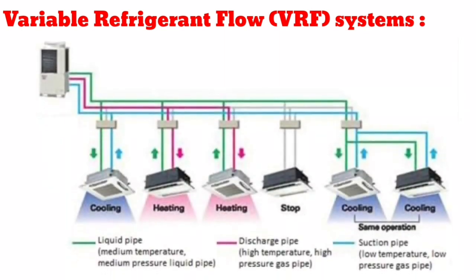Variable refrigerant flow VRF systems are similar in appearance to multi-split air conditioners. What makes the difference is the number of indoor units and the control function. A multi-split system is generally limited to about 10 indoor units, whereas VRF systems can connect to more than 50 indoor units on a single outdoor condensing unit. VRF systems use proprietary temperature control devices for efficient flow of refrigerant, with temperature control available at every indoor unit, and the outdoor unit adjusting compressor load based on heat load from various units.